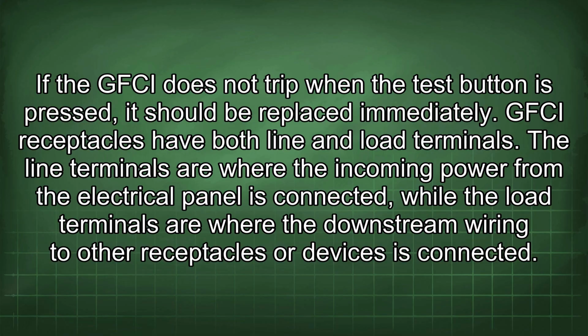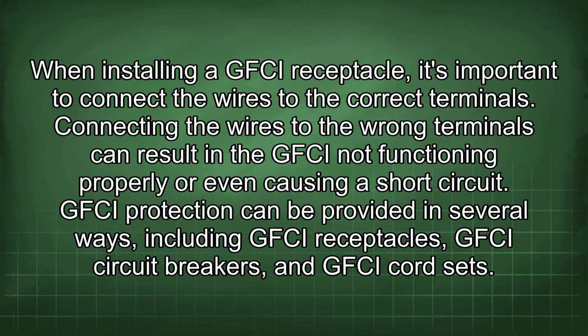GFCI receptacles have both line and load terminals. The line terminals are where the incoming power from the electrical panel is connected, while the load terminals are where the downstream wiring to other receptacles or devices is connected. When installing a GFCI receptacle, it's important to connect the wires to the correct terminals. Connecting the wires to the wrong terminals can result in the GFCI not functioning properly or even causing a short circuit.